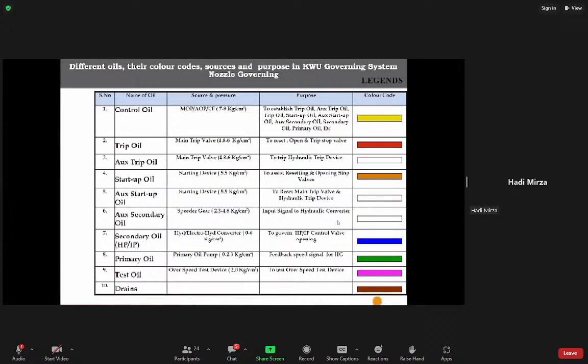Secondary oil is the input signal for the servo motor of the control valve. So auxiliary secondary oil is the input for the hydraulic converter. Primary oil is a feedback signal. It is a feedback from the turbine, basically. It acts as a feedback signal for the hydraulic governor. Test oil, we just inject into the overspeed trip device. For that, test oil is generated.